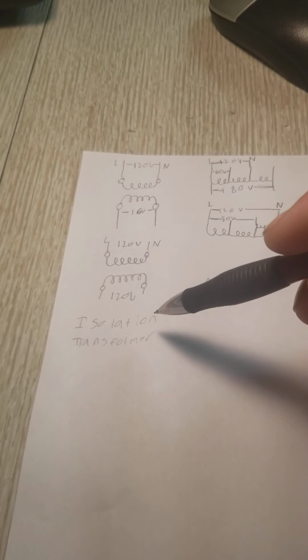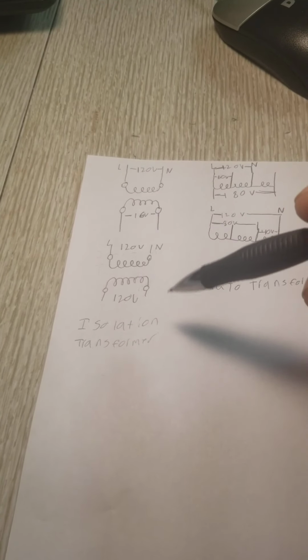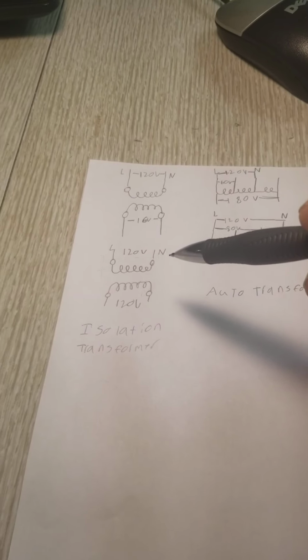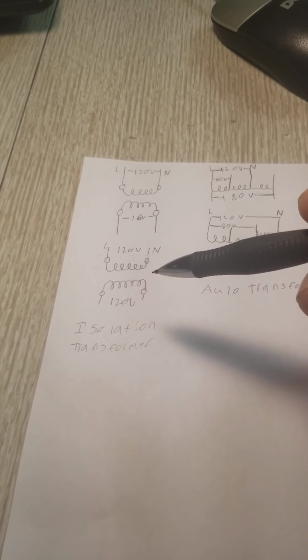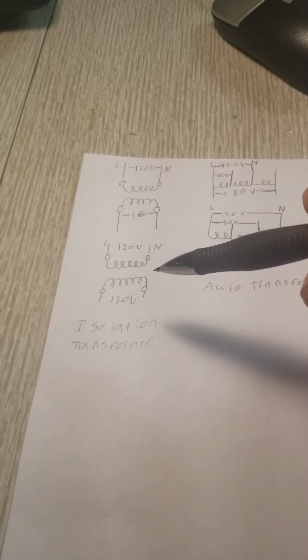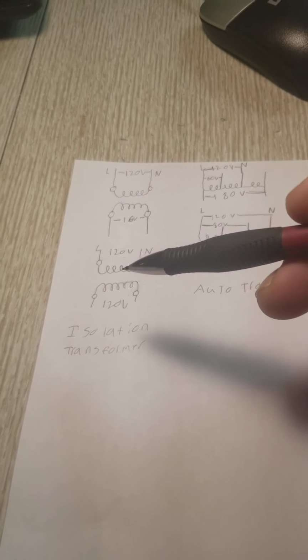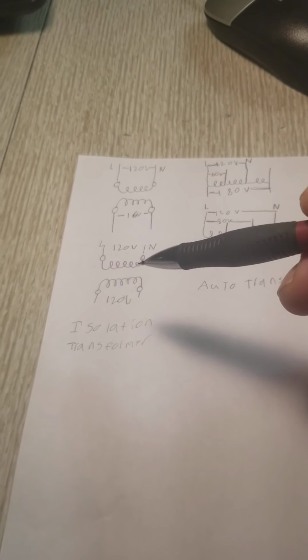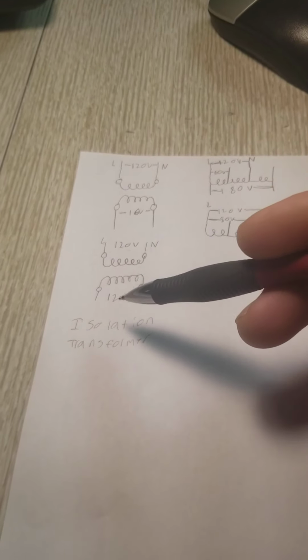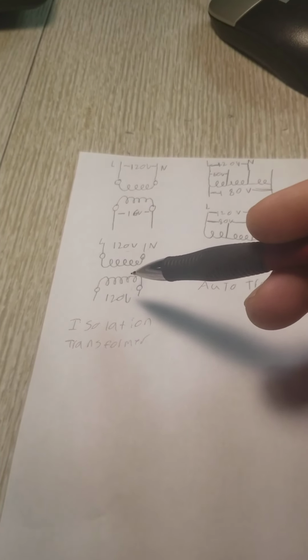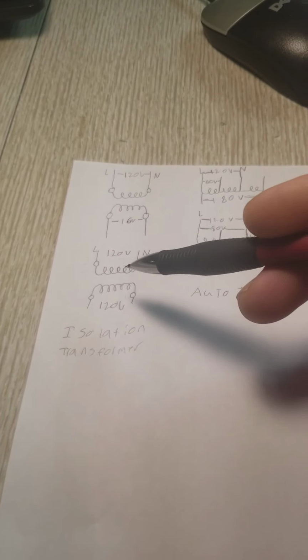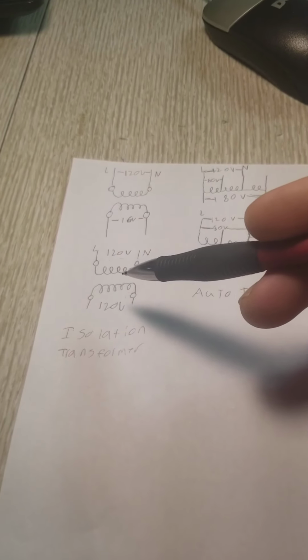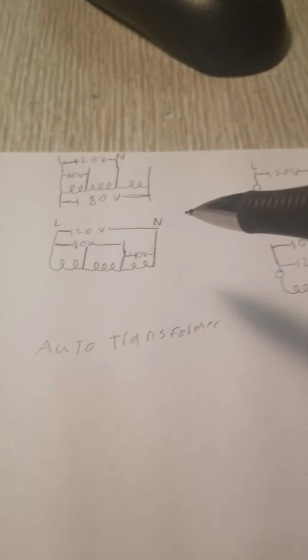That's actually desirable in some cases where we don't want any kind of electric tie to the source, perhaps for sensitive medical equipment or something like that. So often when somebody just says isolation transformer, they might be referring to just a straight 1-to-1 ratio transformer like this that's only there to provide a degree of electrical separation from the utility or whatever else the source might be. Now, these are auto transformers here.